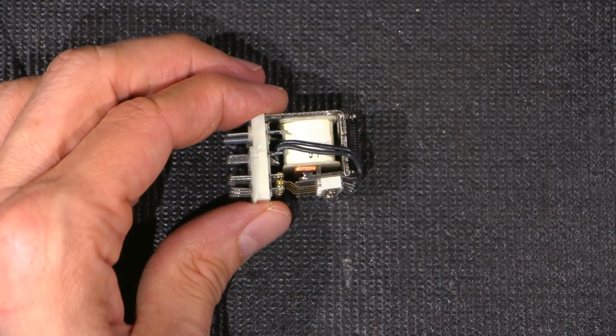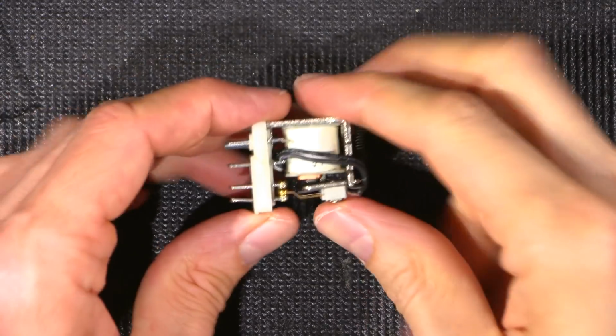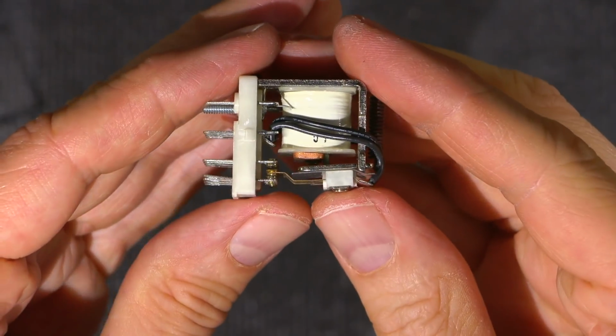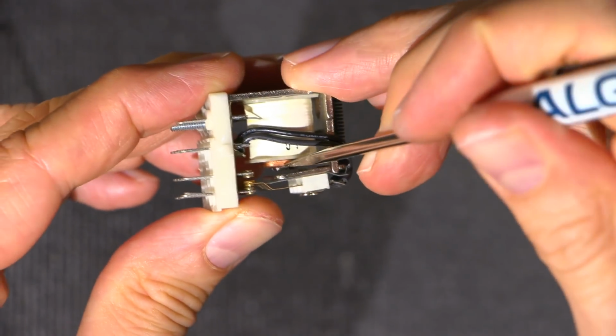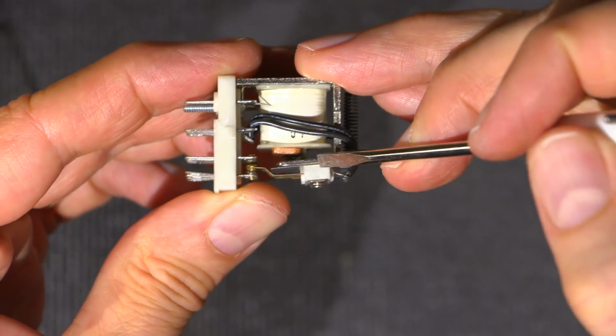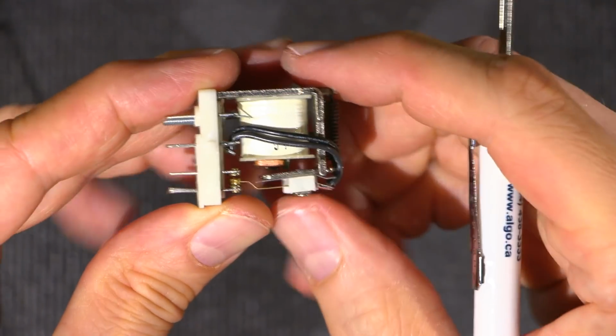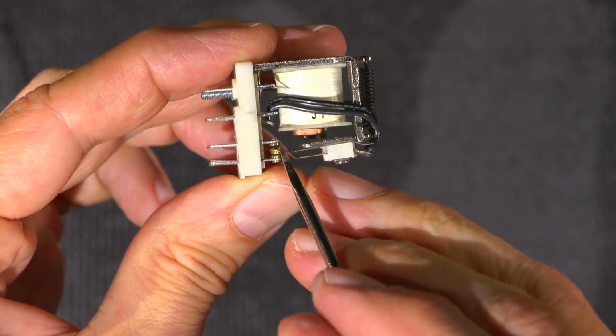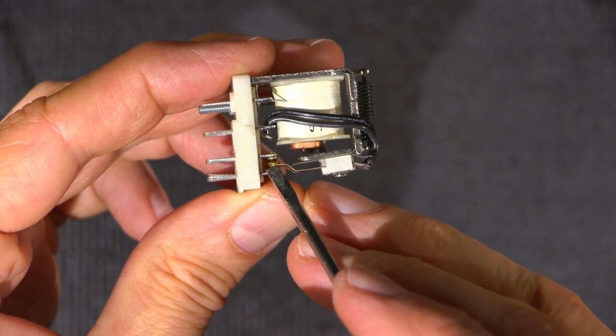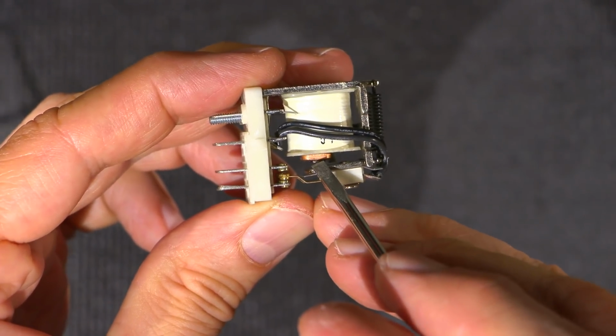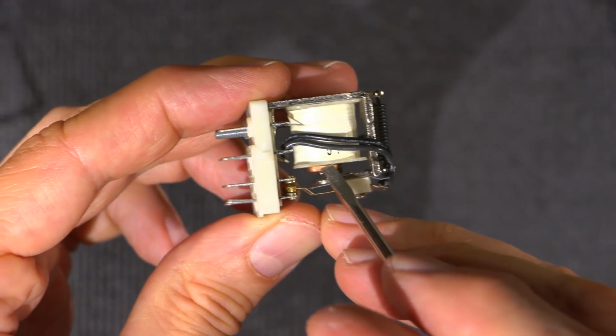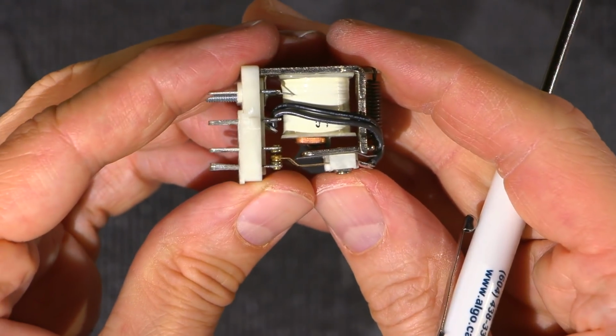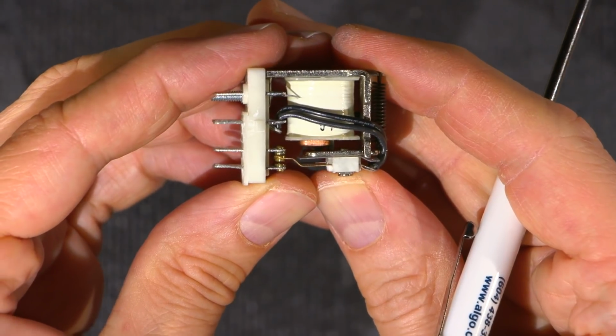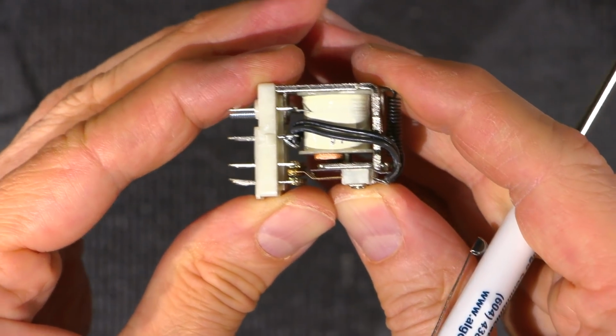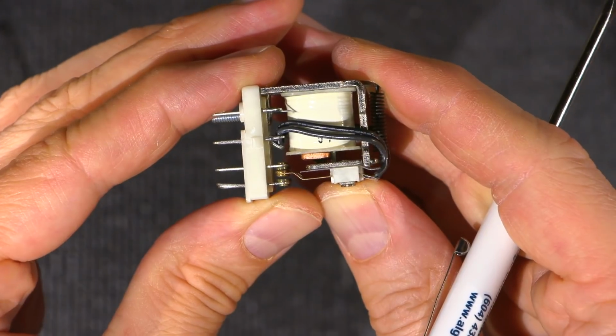Now, one of the things that needs to be noticed, I don't know if I can get in any closer with this lens, I can't. Another thing that needs to be taken into consideration is you can see we have the center of the relay here, which is the magnet, all right, and then we have the arm here. So now you'll notice, watch the contacts on the bottom. Watch this contact, you'll see it come into contact here, but you'll still see a space between the actual electromagnet and the arm. So now it's already making contact. Look at all that space in there, right? I can still close it. See that?